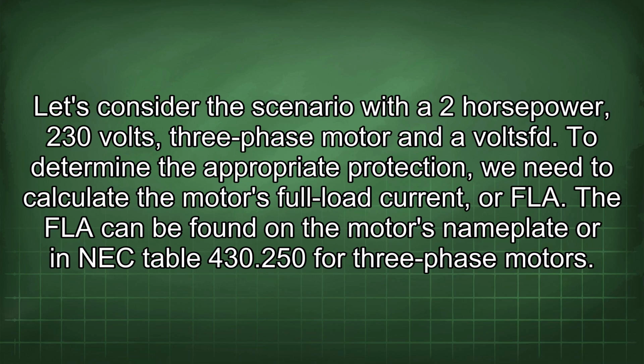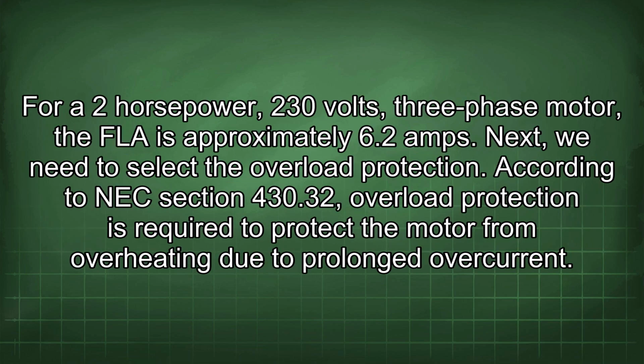Let's consider the scenario with a 2 horsepower, 230 volts, 3-phase motor and a VFD. To determine the appropriate protection, we need to calculate the motor's full load current, or FLA. The FLA can be found on the motor's nameplate or in NEC Table 430.250 for 3-phase motors. For a 2 horsepower, 230 volts, 3-phase motor, the FLA is approximately 6.2 amps.